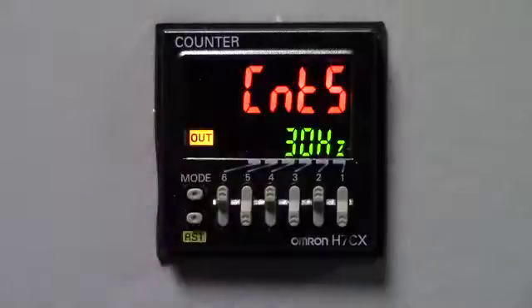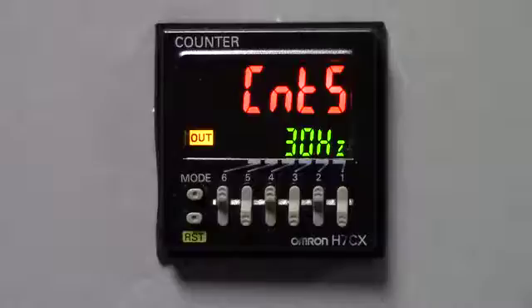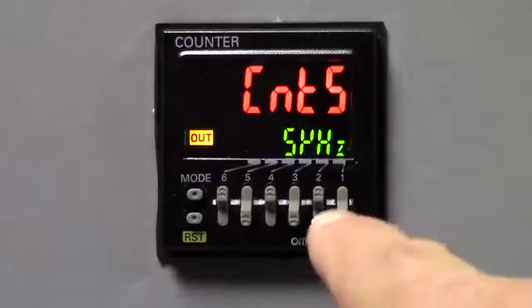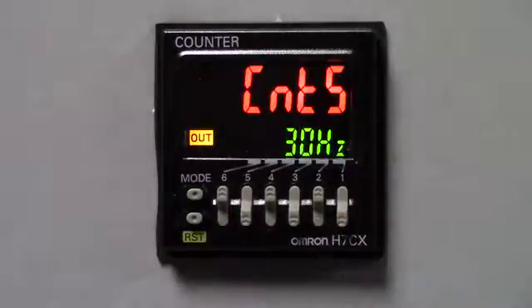The next mode is CNTS. This is the counting speed. There's two speeds to choose from. There's 30 Hertz and 5 kilohertz. Because we are going to be using a push button for our input, we're going to keep it at 30 Hertz. And now we're going to advance to the next mode.